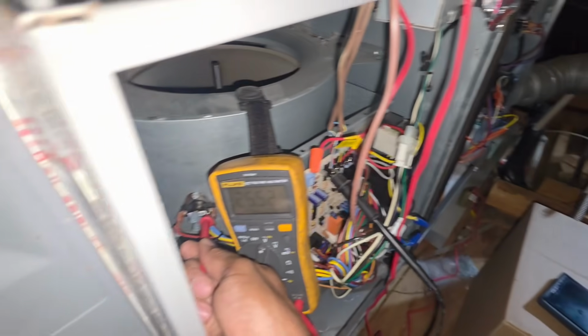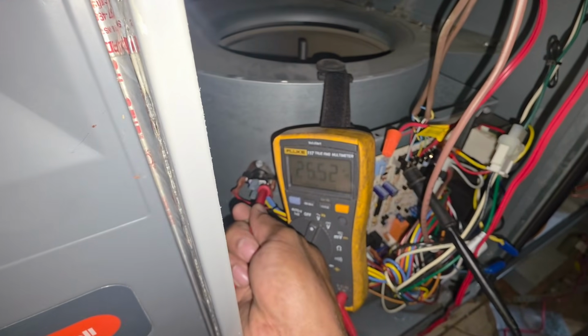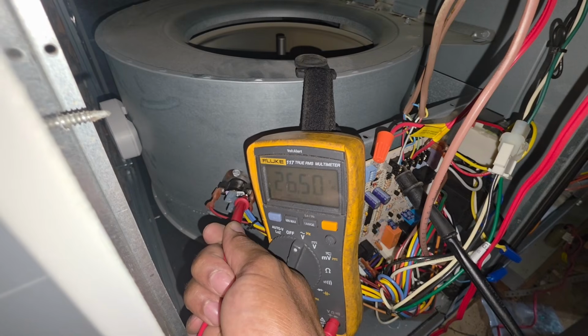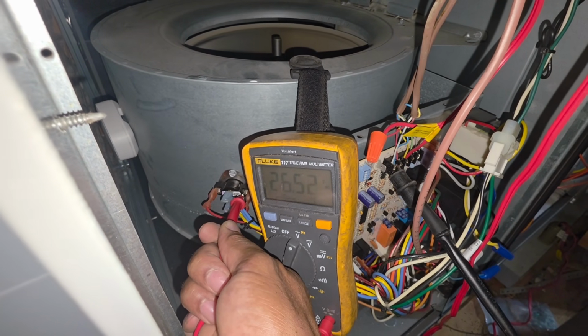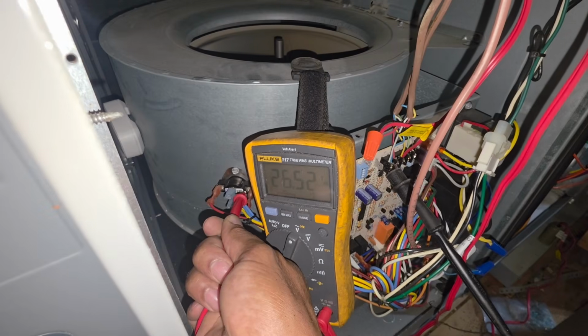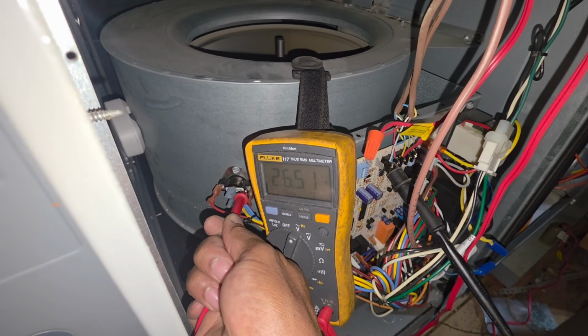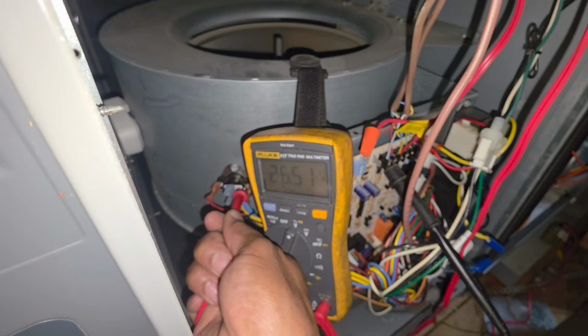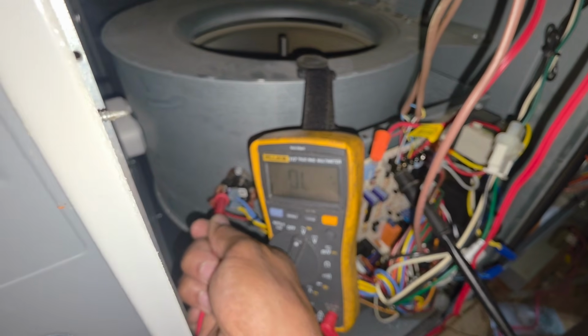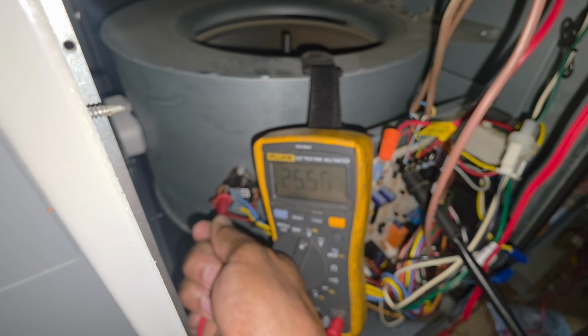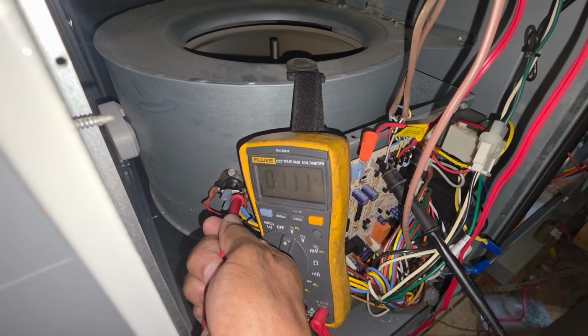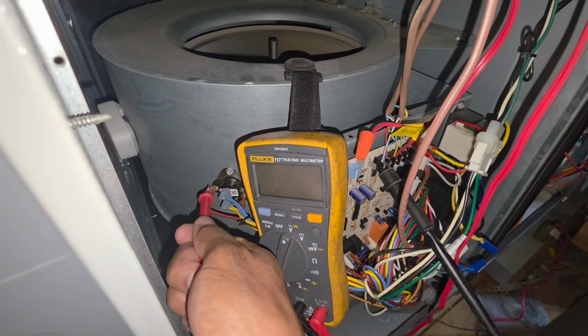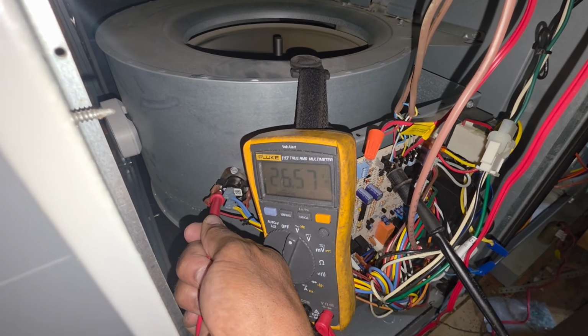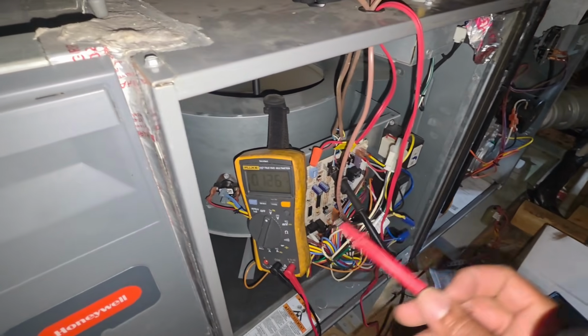But I'm gonna put one lead, remember, I got my pivot on common right there. So I got one lead on one side of that limit switch. You see I'm getting 24 volts. When I say 24 volts, that means at least 24 volts though, to complete that circuit. So now I'm pivoting to the other side of here. You see I'm getting 24 volts. So on either one of these sides, if I was getting 0, but I'm getting 24 right here. I go to the other side of that switch, I'm getting 24. All right. So let's go to the next one.